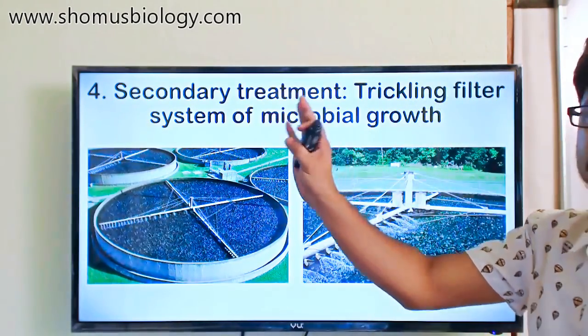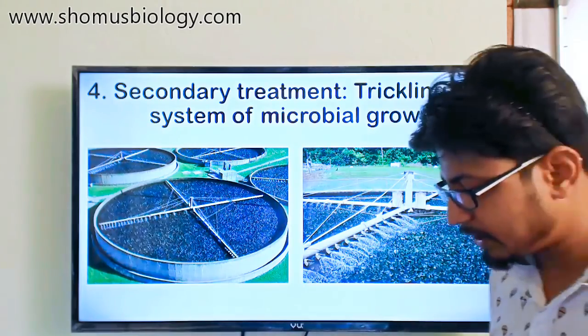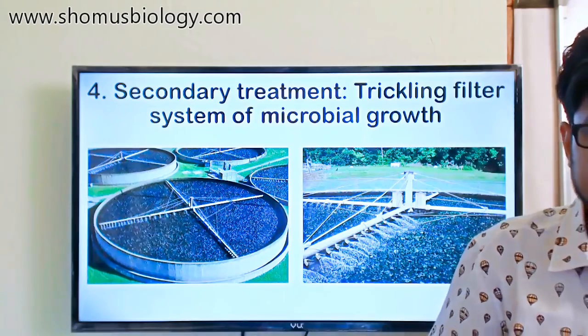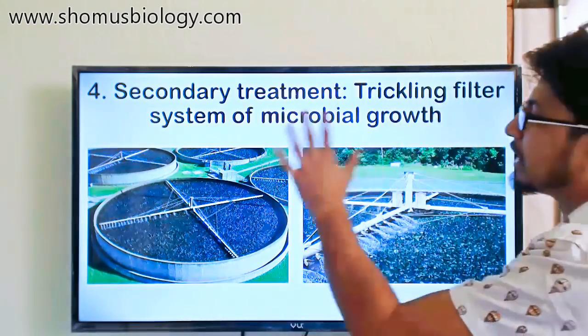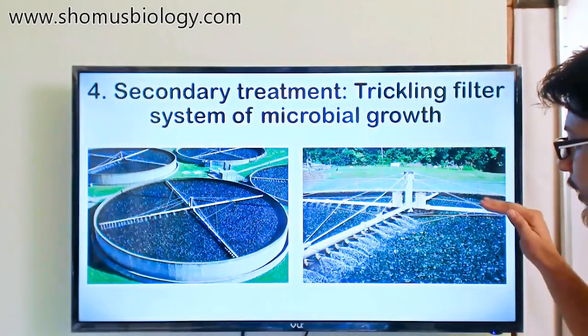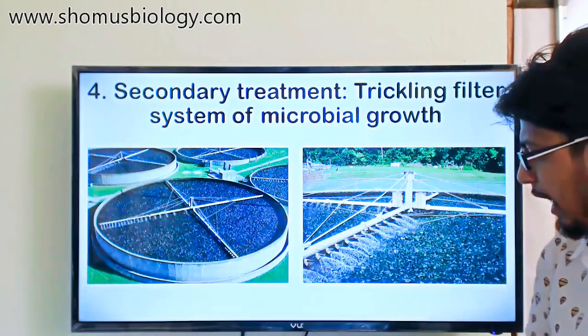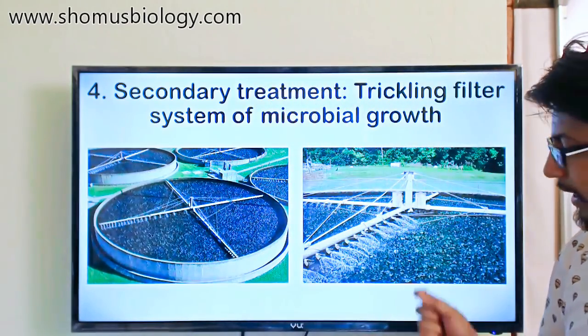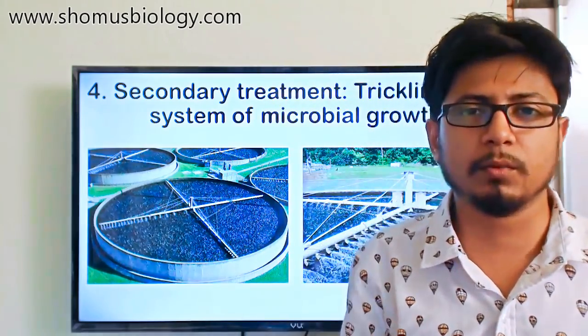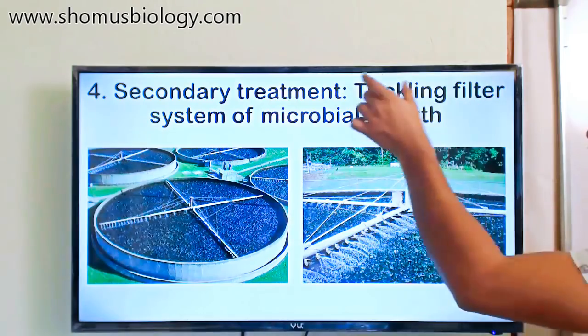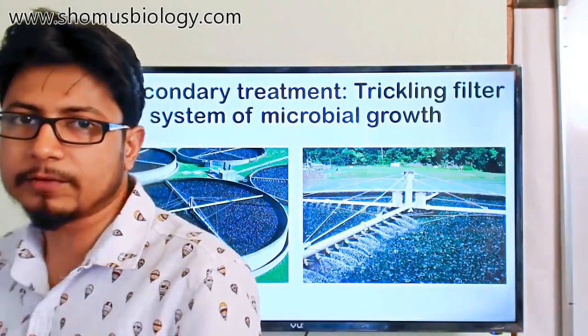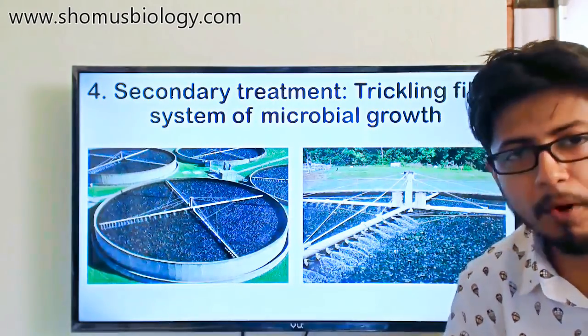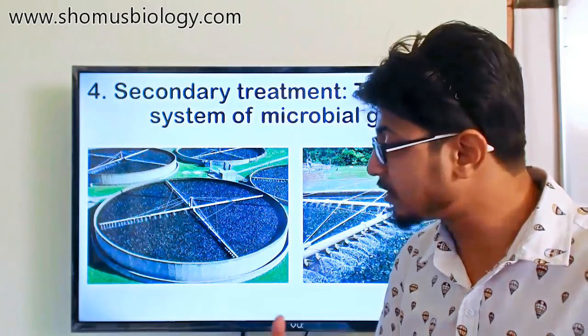This facility is called a trickling filter system for microbial growth. The trickling filter is a mechanical process utilizing the attached growth facility during secondary treatment. The gravel filter creates a large surface area and biofilms coat the surface of the bed. A pipe with a nozzle sprays or trickles wastewater on the surface, and the water travels from the top of the layer to the bottom, where a collecting duct removes the effluent.